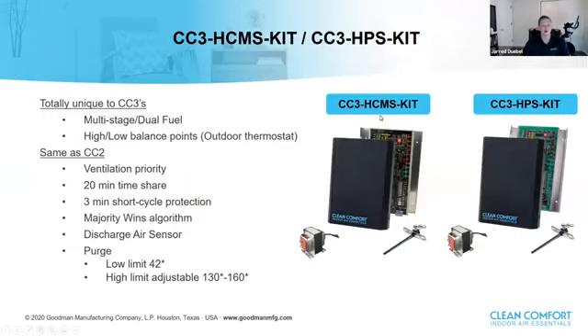And then again, we offer the heat cool multi-stage and then the heat pump series, just like we do with the ESP type panels. The biggest differences you're going to notice, again, there's not going to be those SPS terminals to install that static pressure sensor. One feature I had not mentioned when we were going over ESP is we do offer 20-minute timeshare. It's built into our panel, which it's that way with all of our zone control panels.